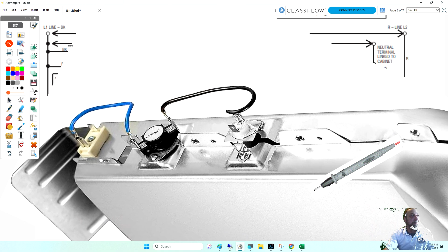Do any of you guys know what that information means on that thermostat? What's the L stand for? Is that the limit is 260, but it should pop around 250? You're close. The limit is 260, which means when the temperature gets to 260 degrees or higher, that thermostat will open. When that thermostat opens, what physically happens? If this opens up, what happens? It cuts off the heating. It cuts off the heater, so now your temperature's dropping. The minus 50 is when the thermostat will close back again. So if it opens at 260, when's it going to close? 210. 210, correct.